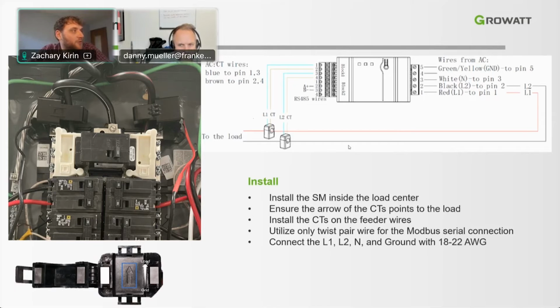The L1, L2, and neutral. So here is an example of how it is wired into the system. The L1, L2, and neutral need to be plugged into the smart meter, and this can be done with either 18 or 22 gauge wire. But you'll also need to make sure that there is a small circuit breaker, 10 amps at the very least. So 10 amps into a circuit breaker into the grid connection. And then the CTs are communicating with the smart meter, and those are pre-wired, so there's no need to worry about wiring the CTs like this.